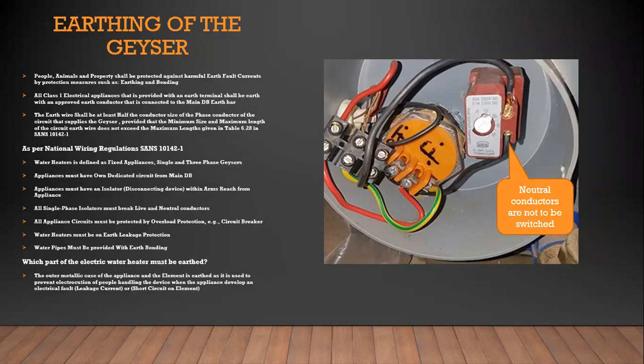Some water heaters, you will find the neutral is wired through the thermostat, which is not according to the regulation. The regulation clearly stipulates that only live wires must be switched through a switch. In this picture I've got here, you've got the neutral through the thermostat, and when you do the basic fundamentals, you'll understand when is a neutral live and when is a live wire live. A live wire is basically always live. A neutral only becomes live with current carrying capacity once there is a load connected. So if a geyser element is on, you will have the same effect on the neutral wire regarding current and voltage as in the live wire. That's why it's important to switch the correct wire.